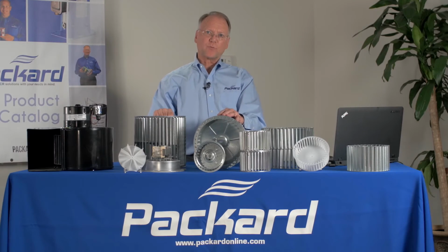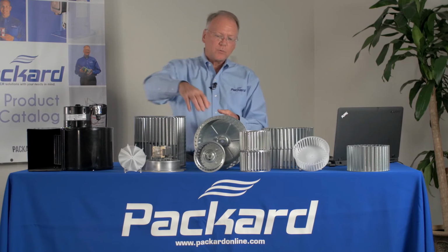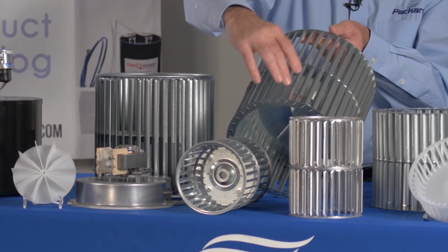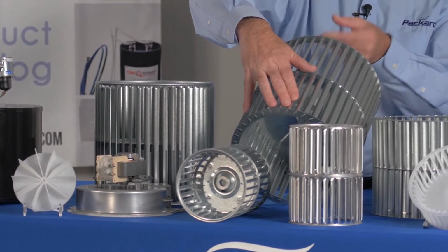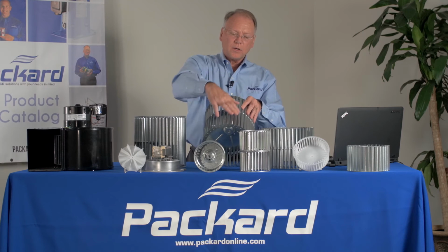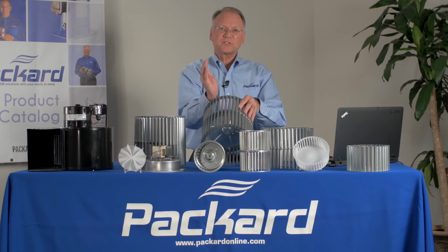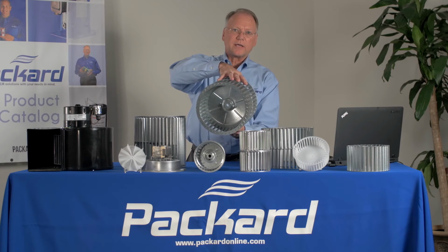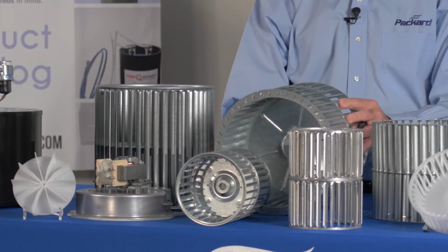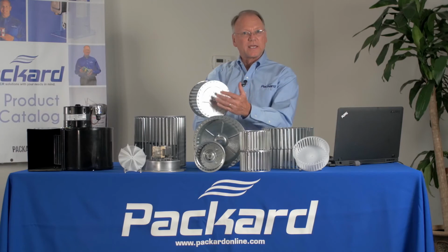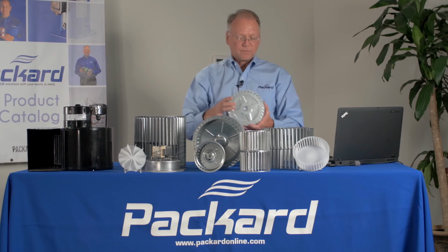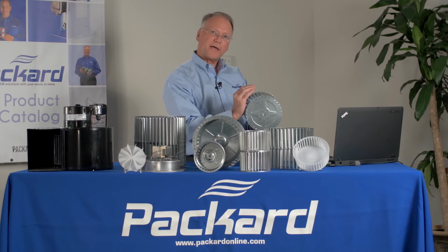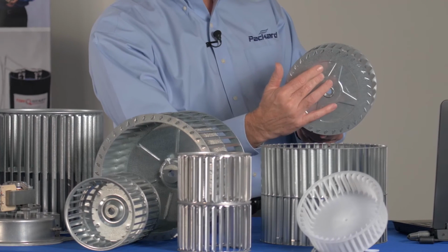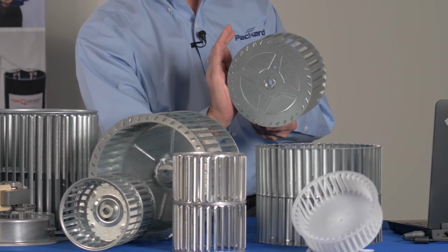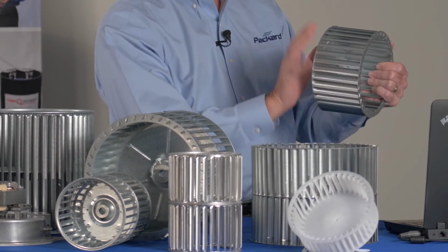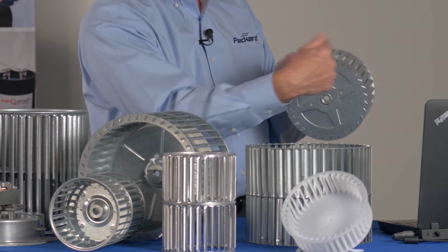The rotation is an important characteristic on a wheel. When you look at a wheel, you'll notice that there are blades, individual blades. Those individual blades are cupped. The rotation of the wheel is the cup side going into the air, cutting into the air. The rotation is determined from the end plate of the blower. For example, with this particular wheel, the blades are cupped at an angle. Looking at the back plate of the blower, the rotation of this wheel would be determined, looking at the back plate, clockwise rotation.